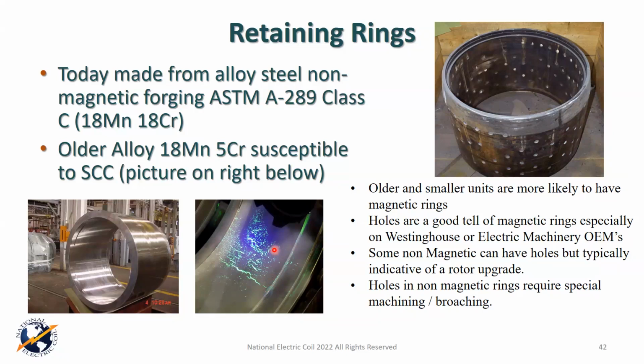But again, in almost all of those cases, the deterioration of corrosion had already started. In most cases, it came back, and the more moisture you had, the more it came back. Okay, and so it's really important. If you have these, you need to put in your maintenance plan to get rid of these and get 18-18 rings. Okay.